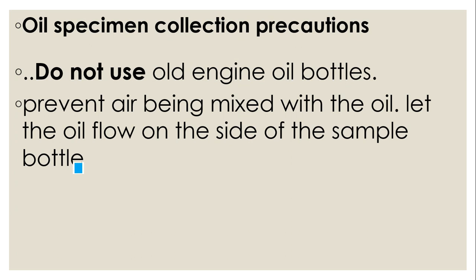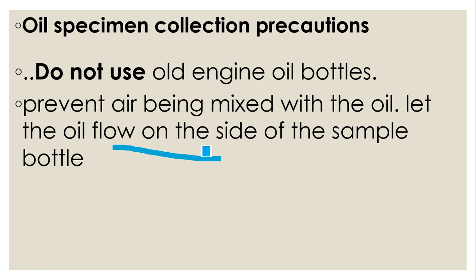Now there should not be bubbles of air. Without making air bubbles, you should be slowly taking the sample in the bottle. Generally we'll be keeping the flow on the sides of the bottle, not directly onto the center. We'll be slowly pouring along the side walls of the bottle, and through that the oil will be flowing down to reduce bubble creation.